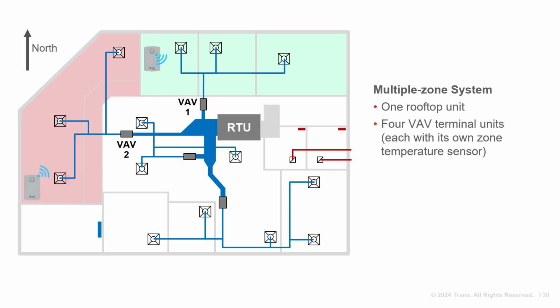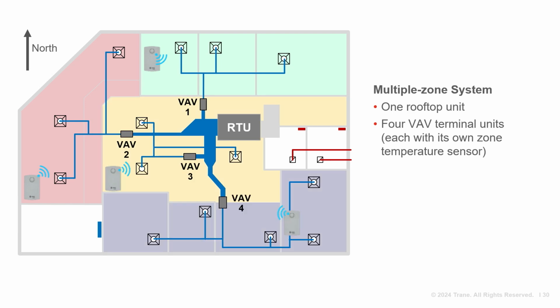One package rooftop serves the entire building, and the supply airflow is ducted to 4 VAV terminals, which each modulate airflow to each of the 4 zones. Zone number 1 is the north side of the building, which includes 2 private offices and a break room. The zone sensor is in one of the offices. Zone 2 includes the area behind the teller counter on the west side of the building. Zone 3 is the customer lobby in the center of the building. And Zone 4 is the south side of the building, which includes a private office, entrance vestibule, and conference room. For this zone, the sensor is in the conference room.